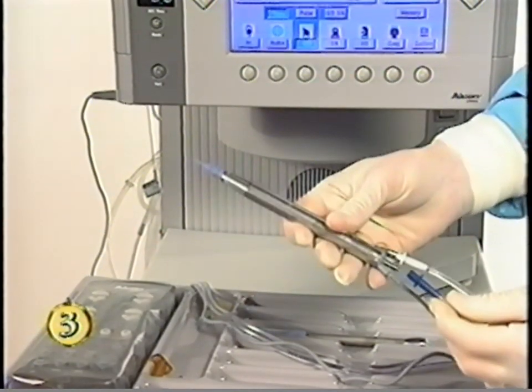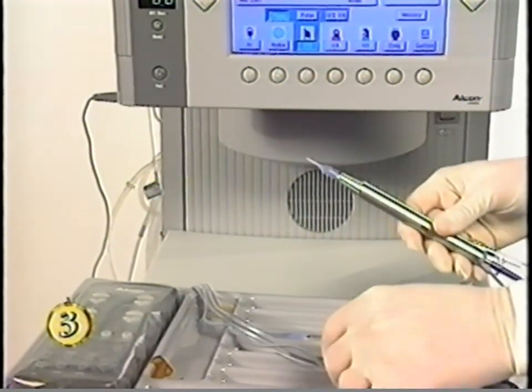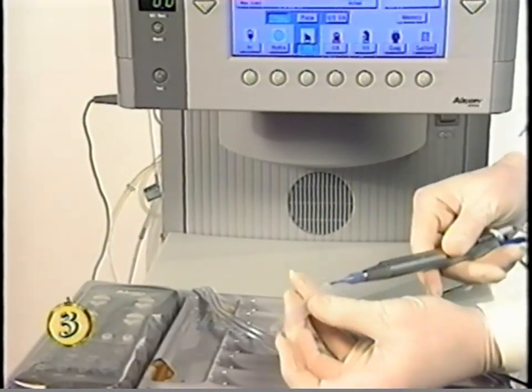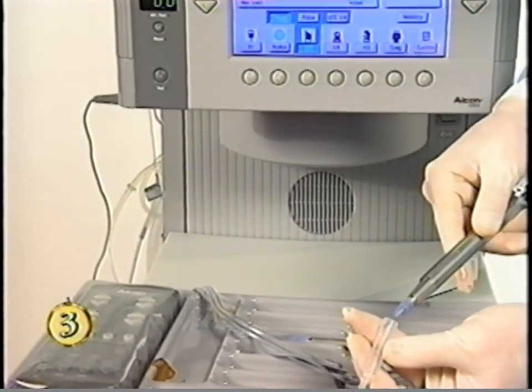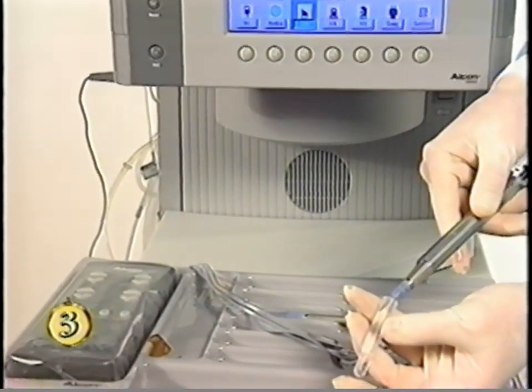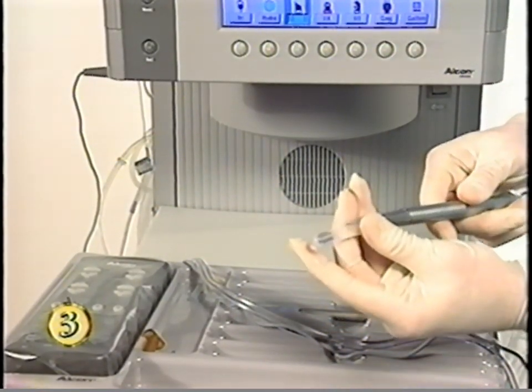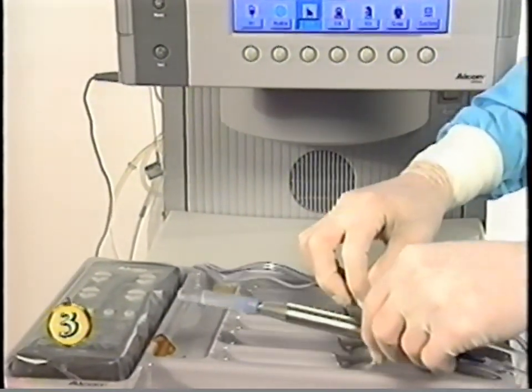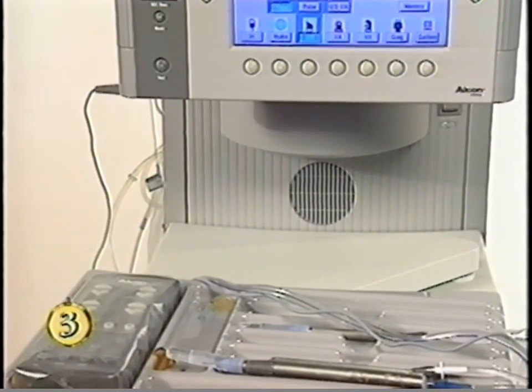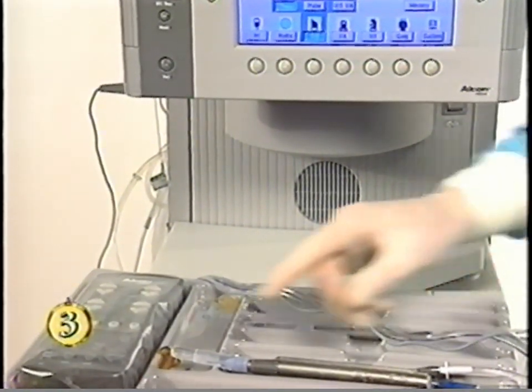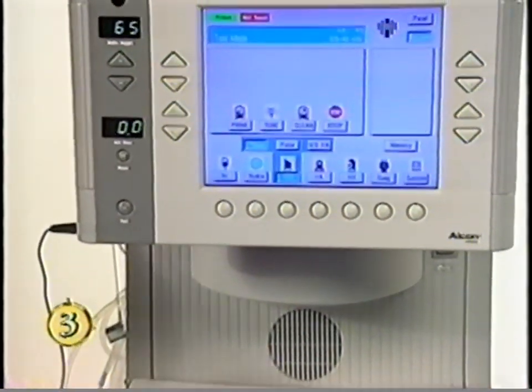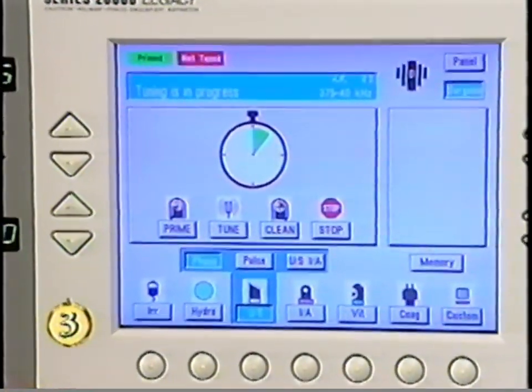Depress the foot switch to position 1 until irrigation fluid streams from the infusion sleeve. Fill a test chamber with this fluid and slide the chamber onto the tip end of the handpiece. Release the foot switch and place the handpiece in the instrument tray. Press the ultrasound mode selection key. Push the test button, then push the tune key.